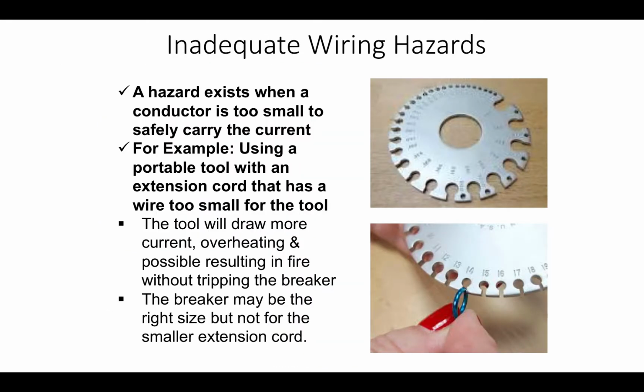We have to be relatively careful also of inadequate wiring. A hazard can exist when the conductor is too small to safely carry the current. For example, using a portable tool with an extension cord that has a wire too small for the tool. The tool will draw more current and overheat, possibly resulting in a fire without tripping the breaker. The breaker may not be the right size for the smaller extension cord.